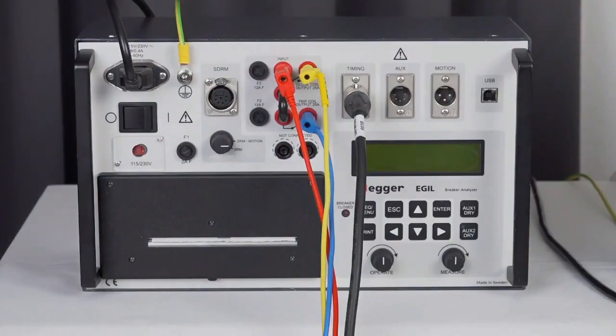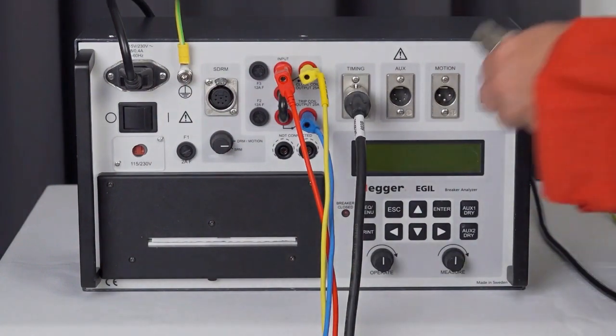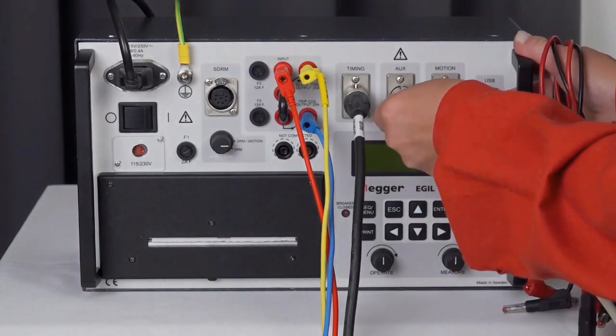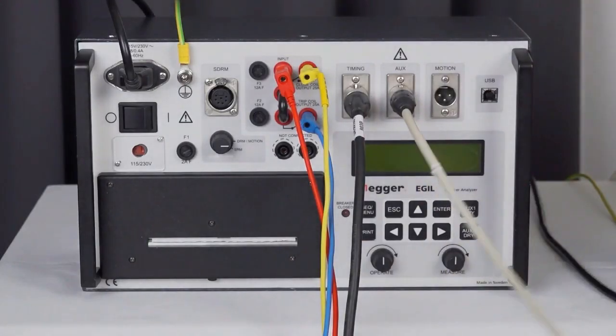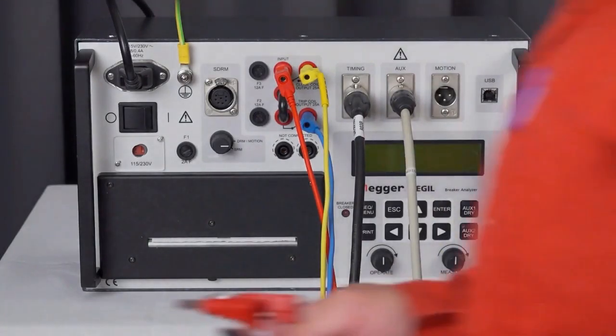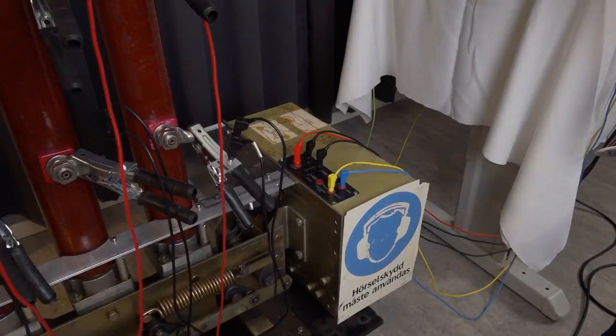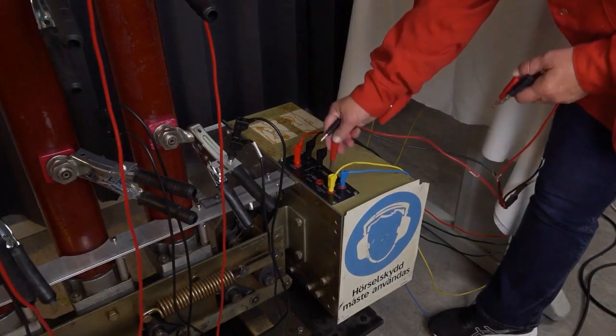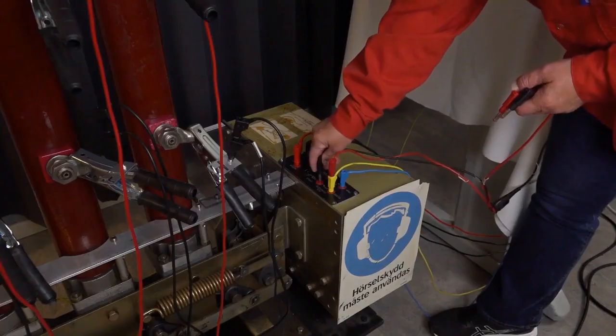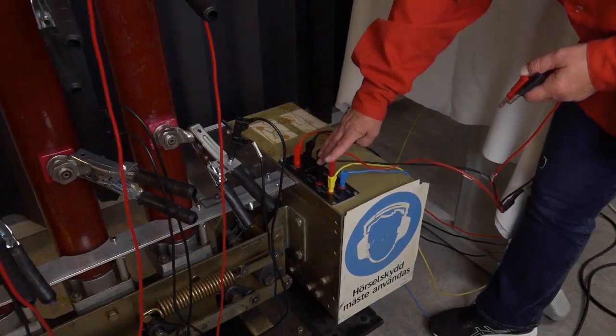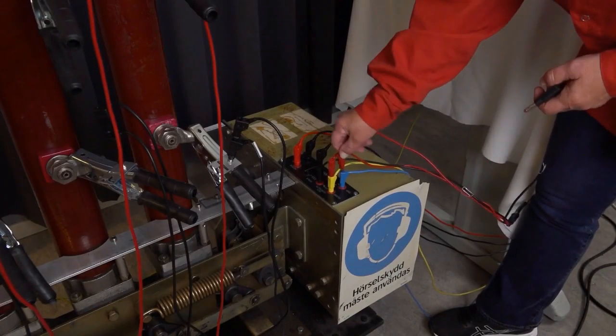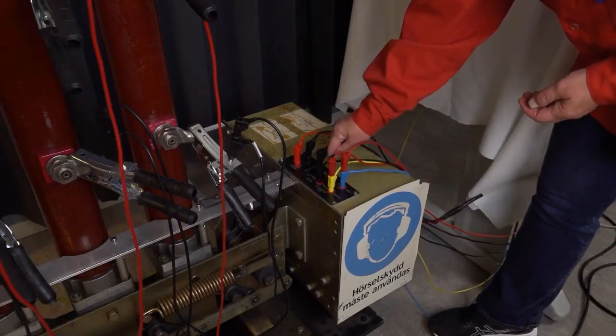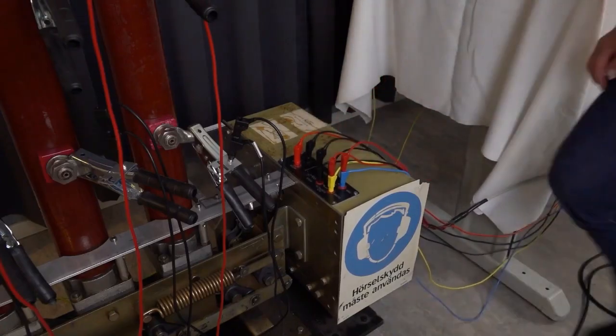I continue with the auxiliary contacts, and I connect the auxiliary contact on the instrument. And on the object, I connect the auxiliary contact timing over the close contact and over the opening contact.